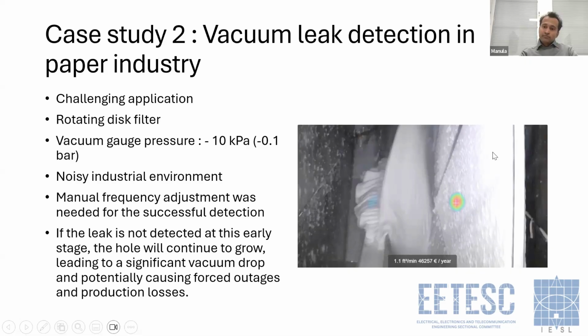these leaks. This is at very low vacuum pressure, and the disc is rotating as well when we are detecting. So it is a bit tricky to detect this kind of very small leak. The environment is noisy and the disc itself is rotating. So I had to play a little bit with the frequencies in this case, because most of these cameras have the facility for the user to define the frequency range in which you want to measure. So the user can do kind of trial and error to detect this kind of challenging application.